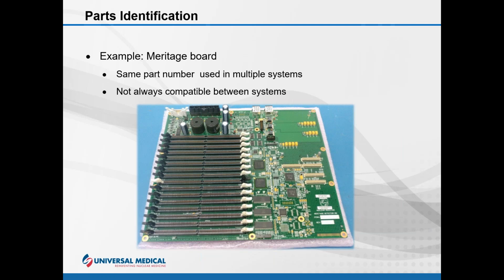Usually one is the part number, possibly the revision and serial number. On this particular part, there's two part numbers. There's one, which is an ADAC 4x4 number, which is an older number issued by ADAC. And then the other number is the Philips 12NC number, which is the newer number. Both of these part numbers are valid, and your vendor should be able to cross them with each other. And out of the three systems using this type of board, we've found that the BrightView can have some compatibility issues and should use the same revision or higher.